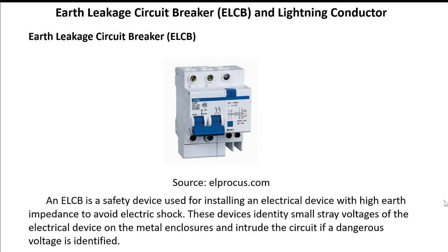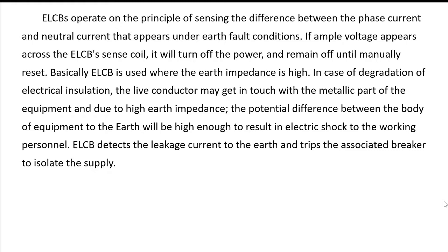These devices identify small stray voltages of the electrical device on the metal enclosures and interrupt the circuit if a dangerous voltage is identified. Here, this is the diagram of ELCB. ELCBs operate on the principle of sensing the difference between the phase current and neutral current that appears under earth fault conditions. If ample voltage appears across the ELCB's sense coil, it will turn off the power and remain off until manually reset. Basically, ELCB is used where the earth impedance is high.